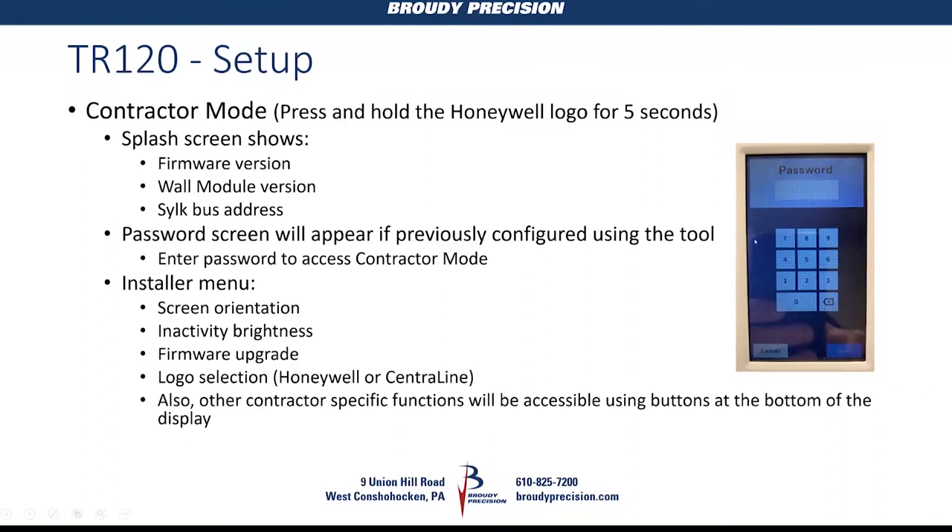One big difference: the TR-71 and TR-75 required up/down arrows to change password numbers, but the TR-120 has a numeric keypad for password entry, and you can assign a custom label for it. From the installer menu in contractor mode, you can change screen orientation, adjust inactivity brightness, do firmware upgrades, and select a logo — either Honeywell or CentraLine. There's no way to import your own logo currently, though there is a micro SD card slot used for firmware upgrades that might allow this in the future.